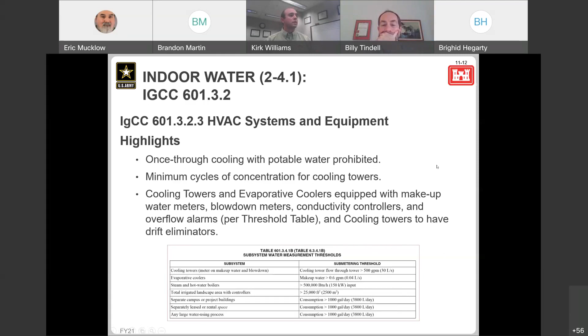The IGCC has a requirement for condensate harvesting. This map I drew isn't the actual units they're talking about at the 1% design condition, but it's an average annual wet bulb map. The IGCC says you're going to do condensate harvesting on units over 65 MBH, a little over 5 tons, capturing the condensate and reusing it. Looking at this map, if you're on the right side of the U.S., you'd probably fall into that realm. I put the Fort Worth weather data here, showing we'd be above that 78 threshold that goes into that realm.